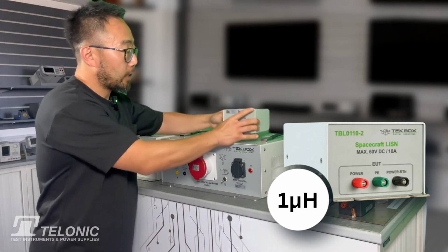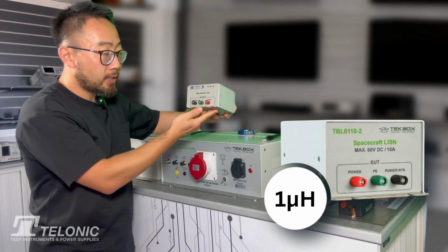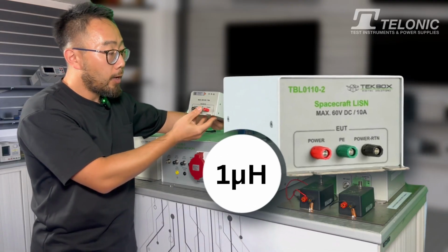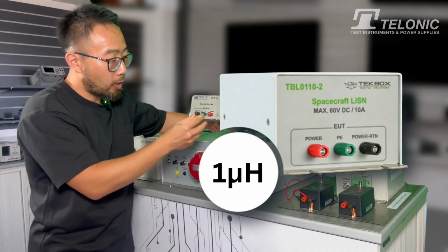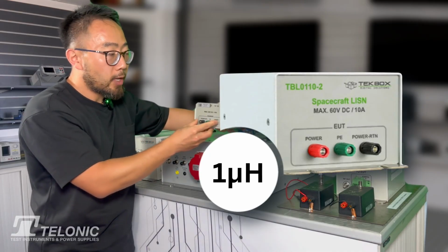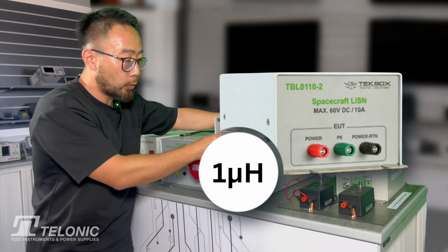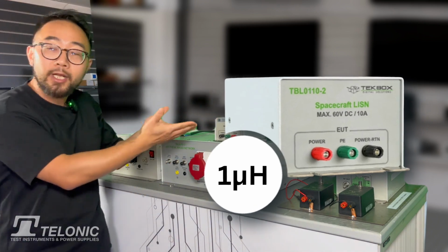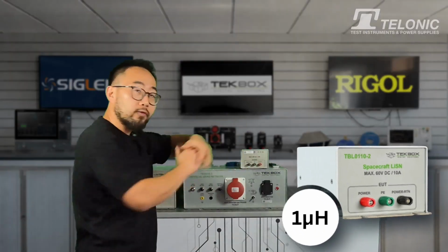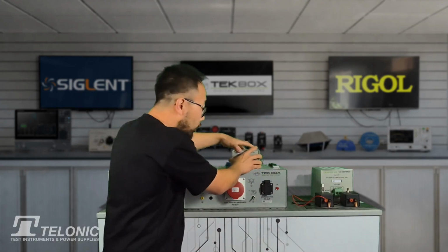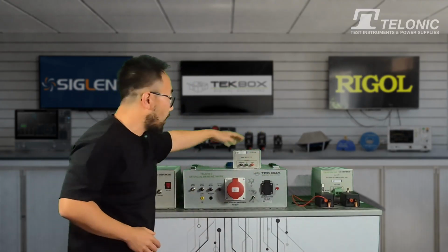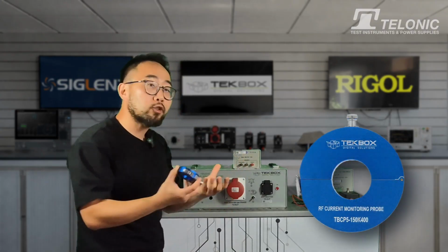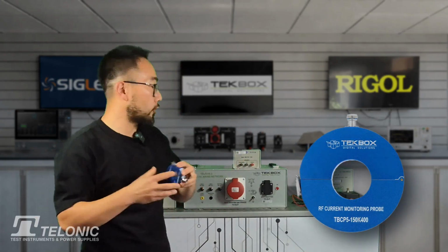Also interesting is that if you look closer, you will see this LISN only has power, PE, which is the earth, and power return. There is no RF output. So in other words, you cannot really measure conducting emission from this LISN. And again, if you go to the standards, you will find this one is only used to stabilize the impedance. The standard says you must use an RF current probe to measure the conducting emission in current form.